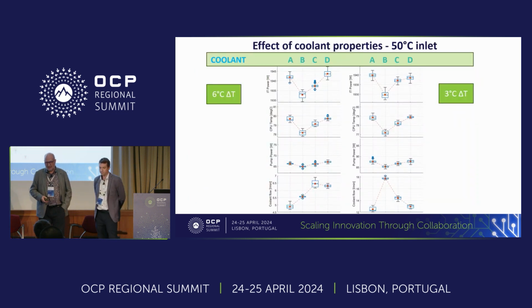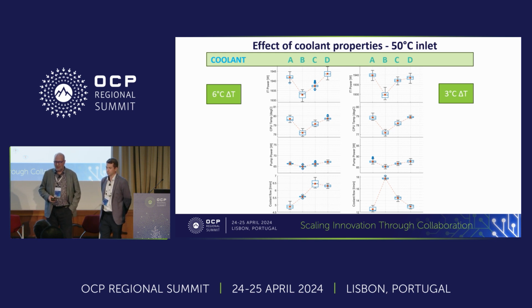Some of the results, yeah. So here we have some of the results. We've got the 4 coolants listed there, and the top graphs, left and right, show different delta T's across, I guess, the heat exchanger. So a small amount of IT, I can't remember exactly, maybe it was six Dell servers that we put in there. And you can see that there's a difference between the power draw of the IT, both at 6 degrees delta T and 3 degrees delta T. So coolant B there drops quite considerably. And that's a result of the current leakages, because the CPU temperature is lower.